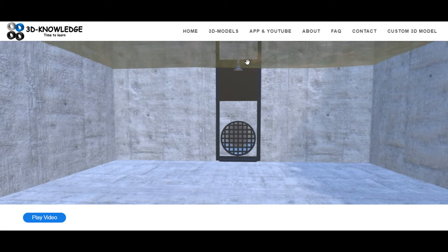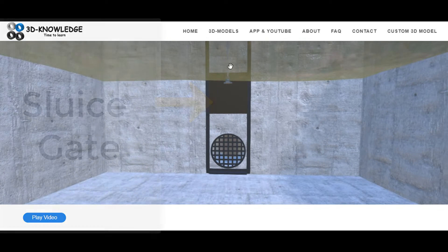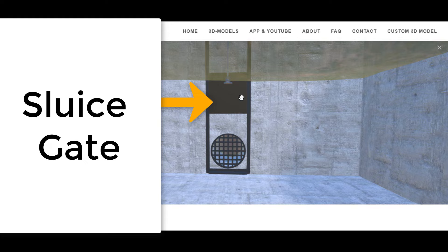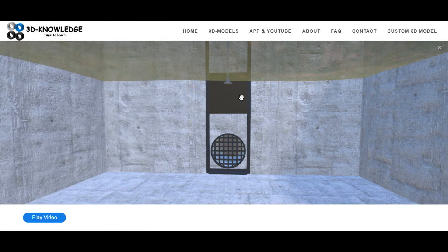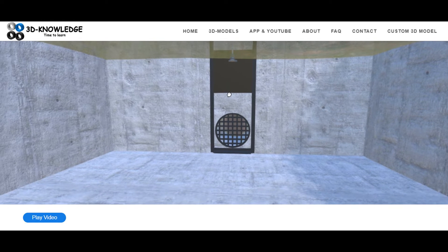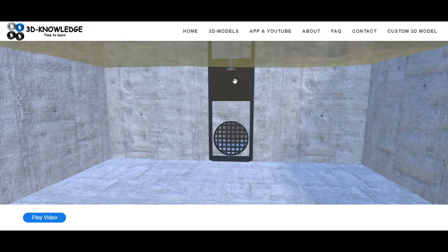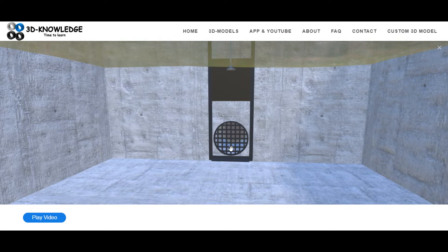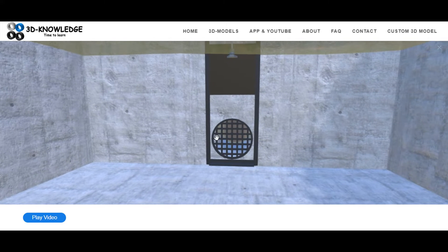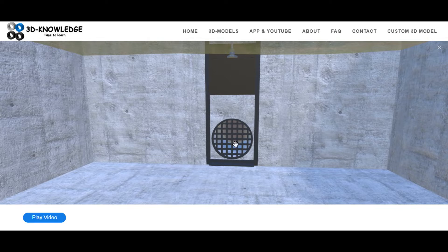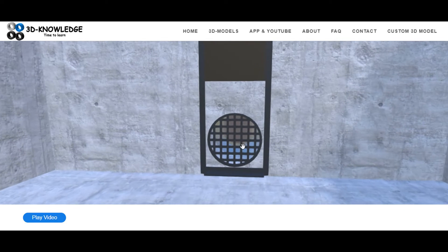So the water is going to flow through this item here which is called a sluice gate. The sluice gate allows us to close the inlet to the turbines. So if there's an emergency in the turbine area or in the power station, we close this gate and that will slam shut and it will hydraulically isolate the turbine so there'll be no more water flowing down in this area and through the pipe.